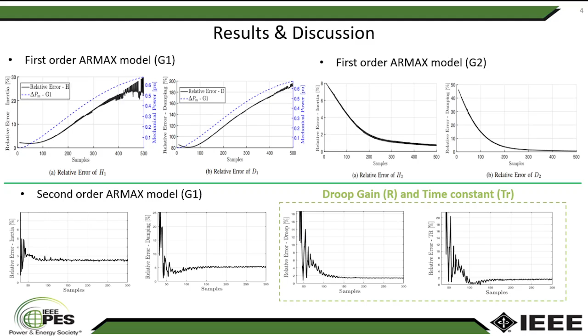Now, in order to estimate the parameters of the turbine governor system and improve the generator's parameter estimation, a second-order ARMAX model is employed. The result shows the relative error for inertia and the damping estimation for generator 1, as well as the estimation of the droop gain and the time constant of the turbine. In this case, the second-order ARMAX model is capable of identifying all parameters with relative error less than 5%. And the advantage of using the second-order ARMAX model when compared to the first order is to eliminate the necessity to clearly identify the instant of the primary frequency control actuation.